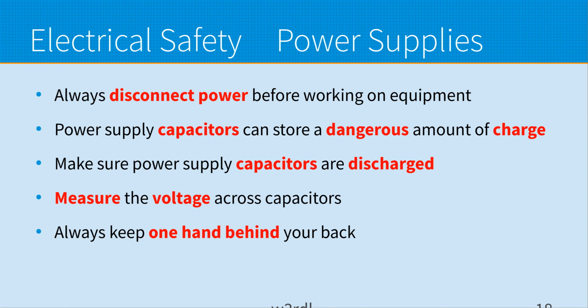So you can measure the voltage on the capacitor to see if it does have a charge on it. I've seen some things on building a little shorting wand that you connect to ground, and you touch it to the terminal and it shorts it to ground to discharge it. It's obviously something insulated from your hand. And the other rule, which is very important, is when you're working on that kind of stuff, try to keep one hand behind your back, because current flowing from hand to hand goes through your heart, and that can cause fibrillation.